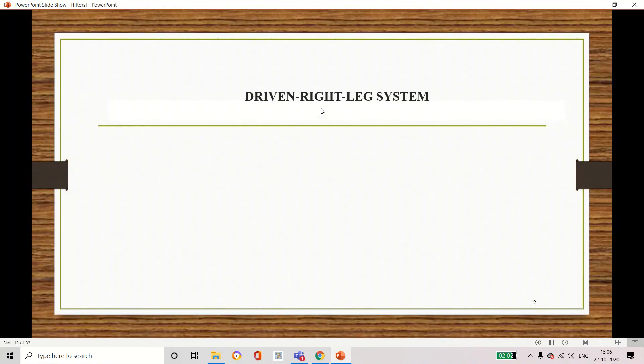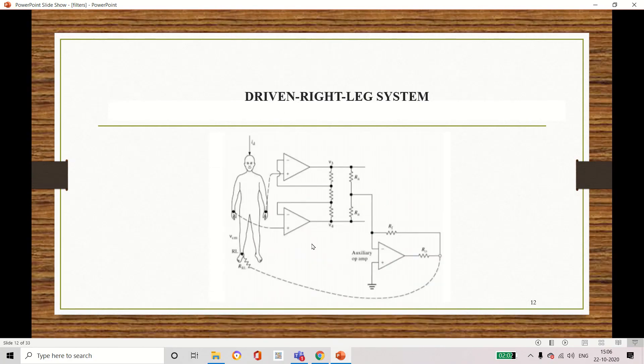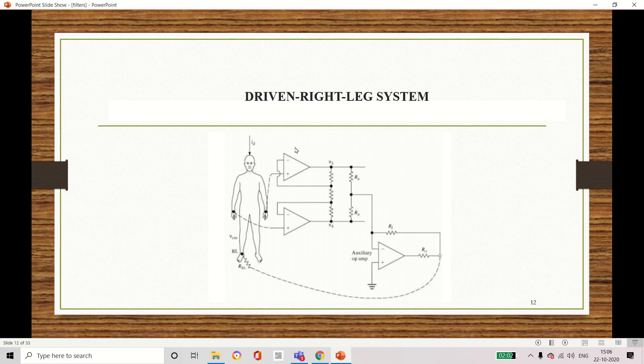Now let us move to the next concept: the right leg driven system. This is the circuit diagram of the right leg driven system. Here we are considering the right leg — mainly focusing on it, which is why it is named the right leg driven system. We take two arms: right and left. We measure the common mode signal, which is amplified using an op-amp, then passed through averaging resistors, inverted, and fed back to the right leg.